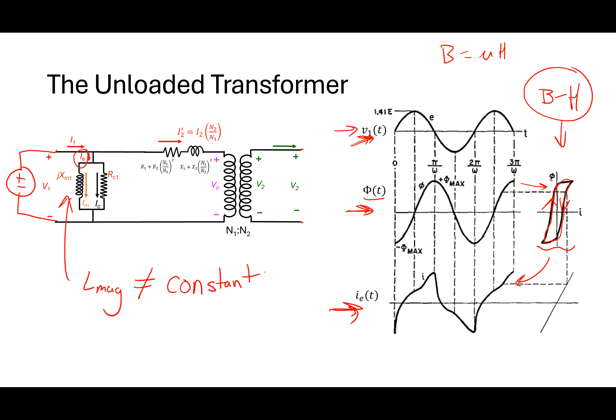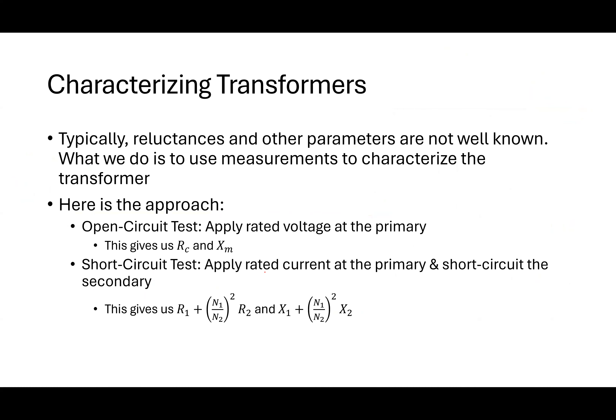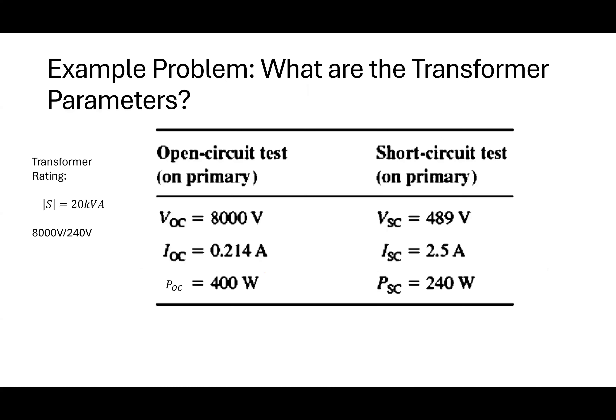In practice, nobody knows all the transformer parameters. What engineers do is perform two tests: an open circuit test and a short circuit test. In the open circuit test, I apply the rated voltage on the primary to figure out the core parameters. Then I apply rated current with the secondary short-circuited to figure out the leakage parameters. This transformer is rated for 20 kVA. The rated apparent power and voltage ratings — 8000 volts primary, 240 volts secondary — let me calculate the rated current.